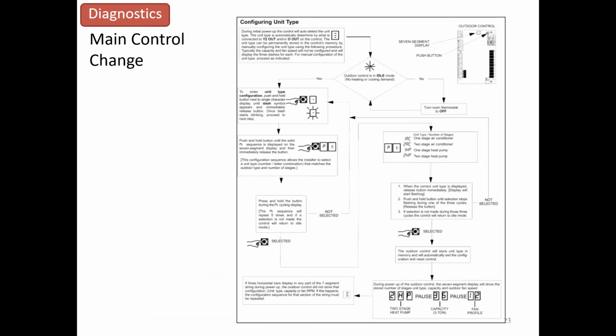If you have a main control board, every once in a while, I have found that we get a scrambled board for whatever reason. I had 2 all of last year, and one of them came from the factory as an air conditioner instead of a heat pump, and it worked fine until we got ready to go to heat season. And the technician called me, and that's what the issue was. So all we did was just went in and reprogrammed it and told it what it is.